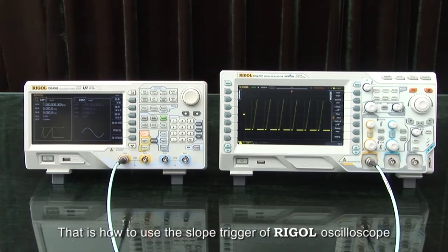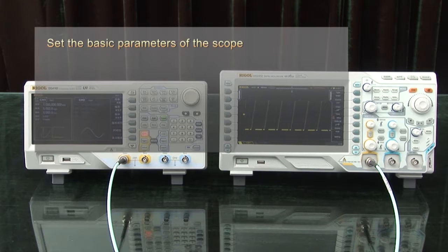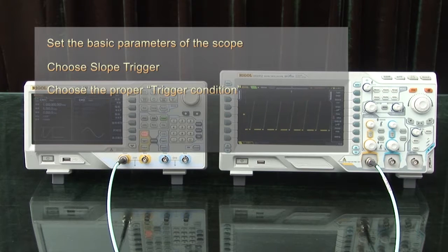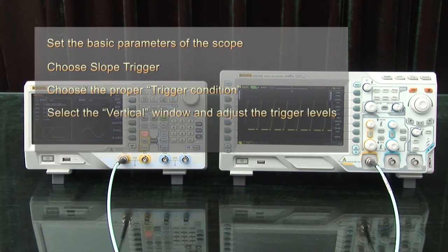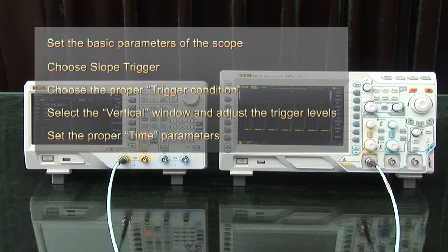That's how the slope trigger for the Rigol oscilloscopes is configured. Here's a summary of the key points: set the basic parameters of the scope, choose the slope trigger, choose the proper trigger condition, select the vertical window and adjust the trigger levels, and then set the proper time frame.